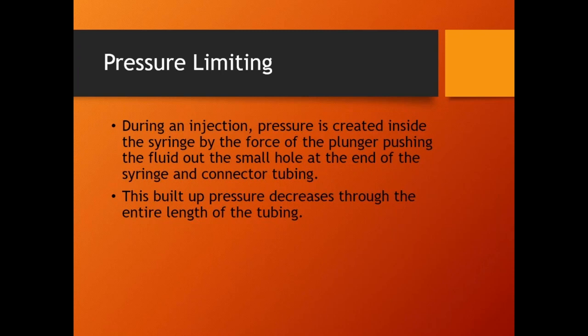Now, there are the three things that I talk about: flow rate, volume, pressure limit. The flow rate and volume are determined by the size of the patient and the procedure that we're actually going to do. When the patient comes in, they know, all right, that's this volume, that's this flow rate. But what determines the pressure? What determines how much pressure they should select for this particular patient? Let me ask you this. It was rhetorical. There are three components from the injector to the patient: my syringe, my connector tubing, then my IV needle or my catheter.